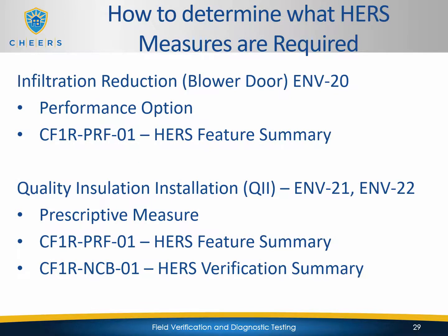The infiltration reduction measure or blower door for the ENV20, it is a performance option. So you're only going to find that on the CF1R Perf 01, and you're going to find that in the HERS feature summary. Now, in the actual blower door training, we're going to take a look at where you're going to find the target values, because you're going to need to know what your test value needs to be. And so we'll cover that. We'll show you where that's found on this CF1R Perf 01, but it's overall going to be found in the HERS feature summary, like we showed in the Title 24 overview.